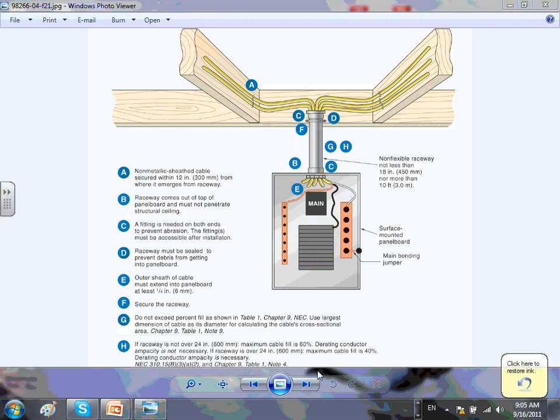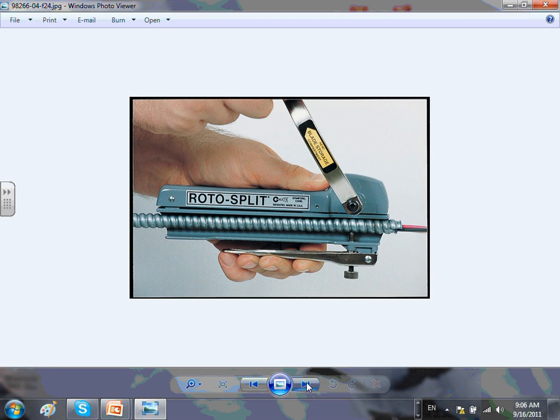MC cable and AC cable — did you wire with AC or MC cable last year? Here's my take: if you are in residential, your wiring method of choice is Romex, no question. If you go to a commercial building, two choices — a cheap project uses AC cable, a good engineering project uses MC cable, which is more robust and better installation. Or of course you can do conduits.